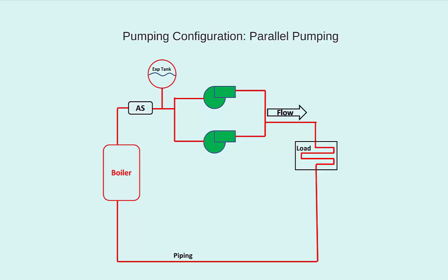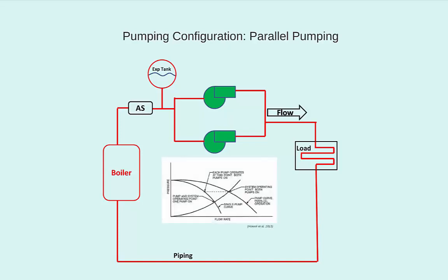There are also times when both pumps operate together when the hydronic system is calling for higher flows. The resultant pump curves with the system curve overlaid looks like this. It is important to note that when pumping in parallel, each pump provides the same pressure increase to the system, but their flows are now additive.